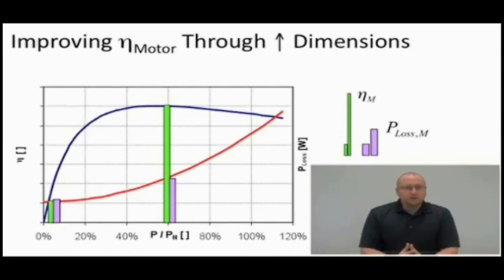If we were to underload that motor, if it was rated for 5 horsepower at 100% load, what if we only loaded it 60 to 70%? What happens to the efficiency? Well, if you look at that curve, you can see the efficiency actually goes up just a little bit. So what we do is we have a motor that's capable of, let's say, 5 horsepower, but we rate it for 3 horsepower to try to get into that sweet spot where the efficiency is a little bit higher. Now we have a more efficient motor. And another way you can think about it is, if a motor is this big, doing a certain amount of work, it's going to heat up and get hot. A bigger motor that's capable of more work is not going to get hot because it can do a lot more. That means it's not going to have losses due to heat, and that's our main source of losses that we want to get rid of.